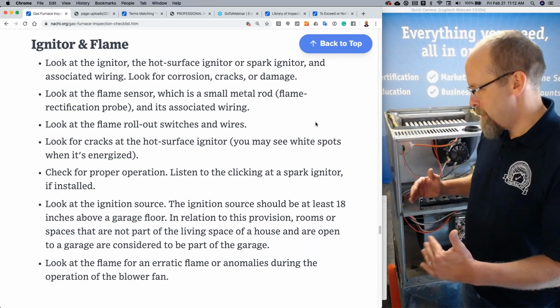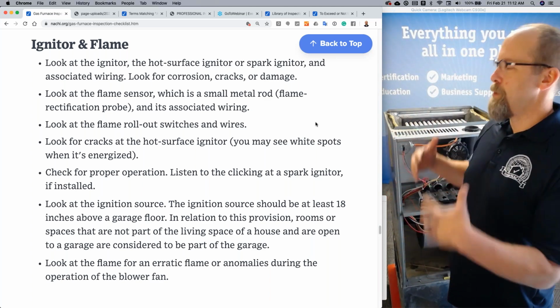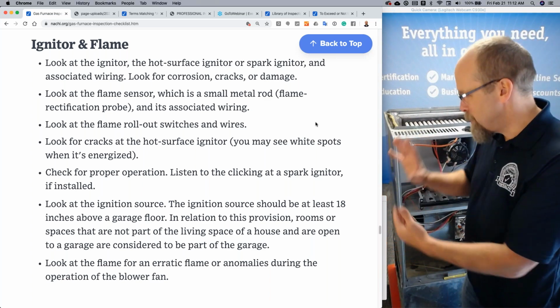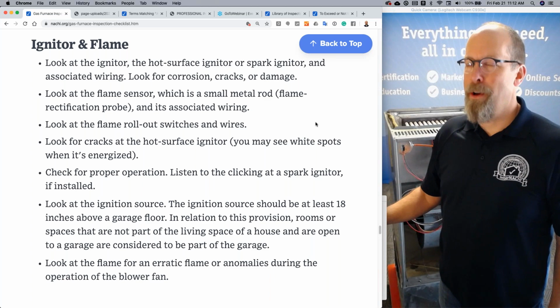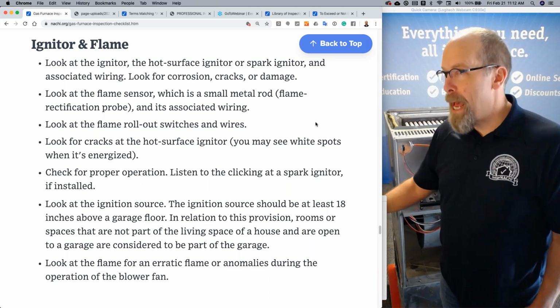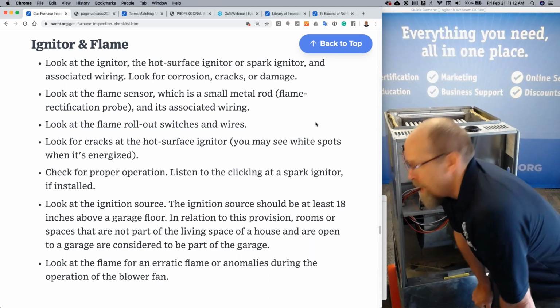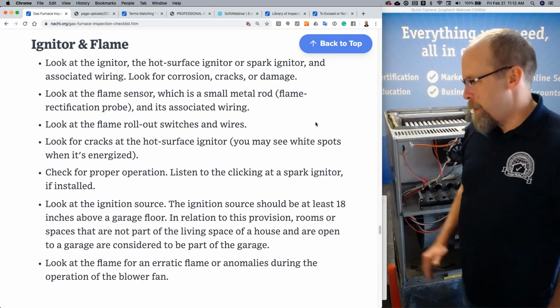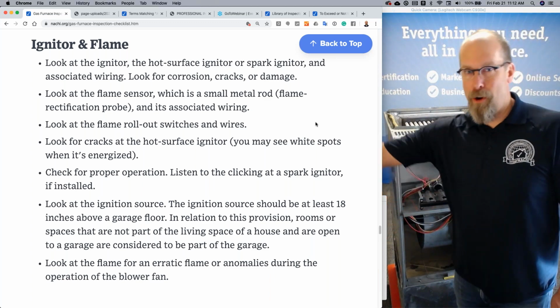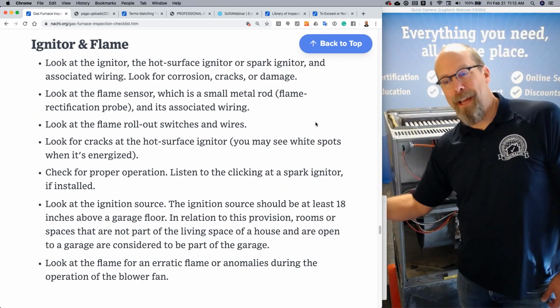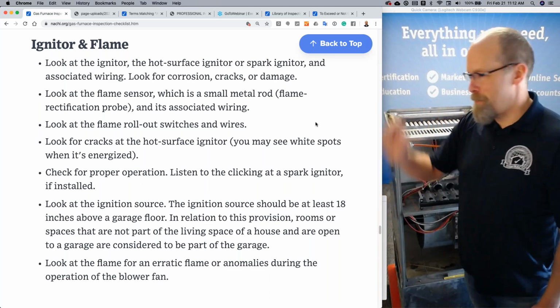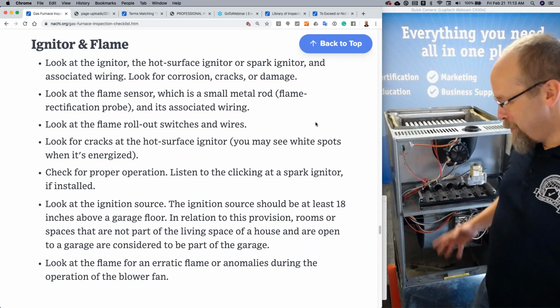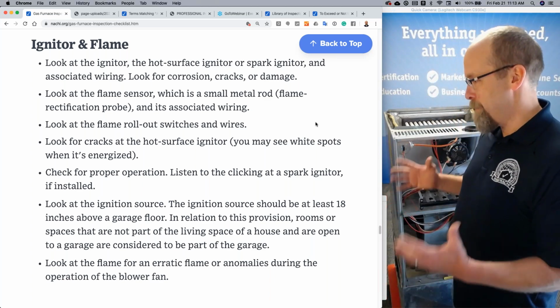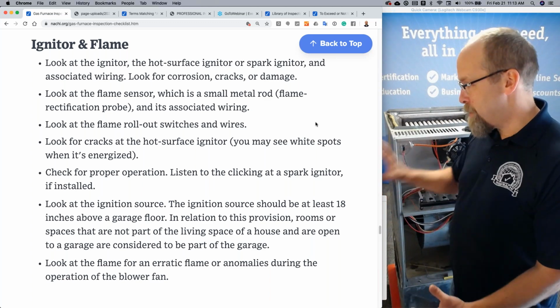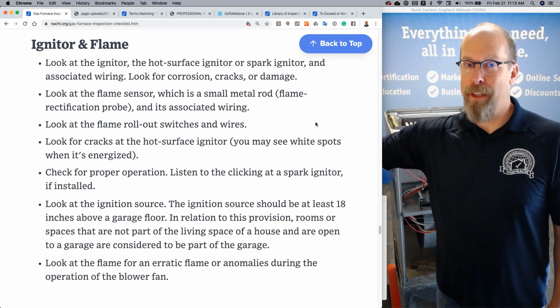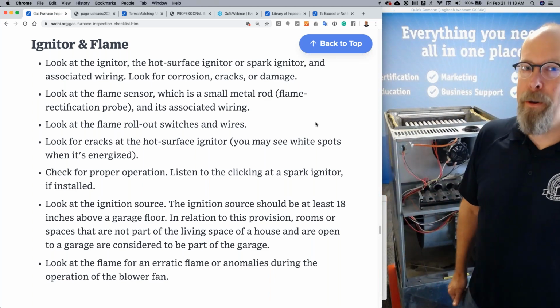If you're in a garage and like you're in a split level, you know how split levels are? So you're in a garage with an attached garage, and there's sometimes an access panel at the rear of the garage of a split level, and that access panel goes to an underfloor crawl space under the living room, right? Well, if that's open, code is saying that's part of the garage. If there's a furnace in there, an ignition source, it needs to be 18 inches above the floor. So the way I see what this is saying is, if you're in an attached garage in a split level, and there's an opening to an underfloor crawl space, and there's a furnace in there, it can't be resting on the floor. It has to be 18 inches high.